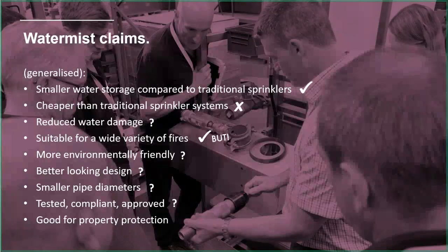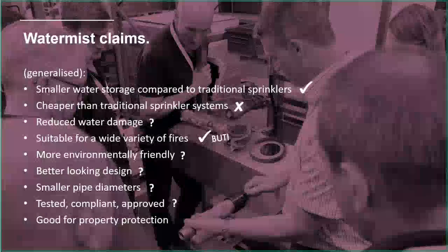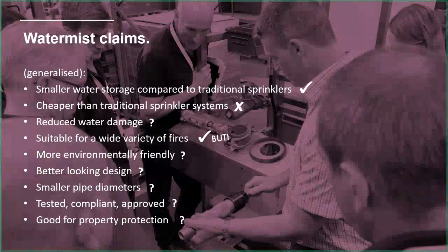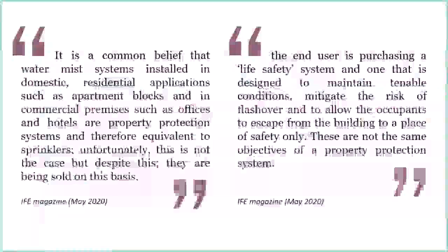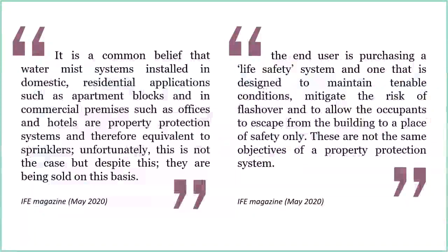And then, good for property protection - that's an interesting one as well. Let's have a look at a couple more quotes from this article I found in IFE magazine. There's a common belief that mist systems are good for property protection and therefore equivalent to sprinklers. This is not the case. All the mist systems that I've seen are for life safety.